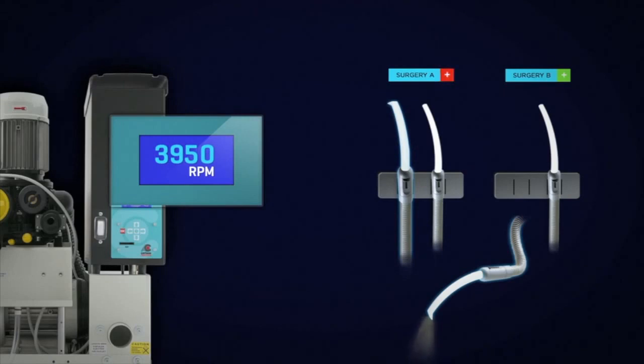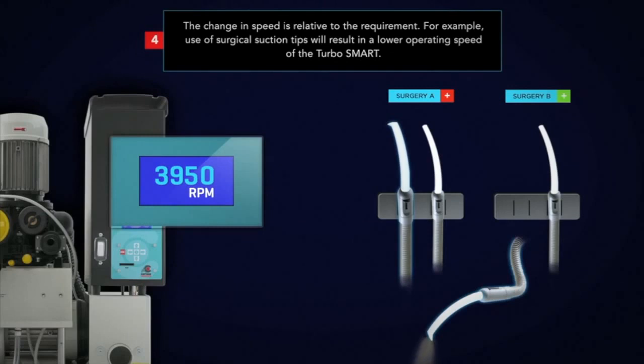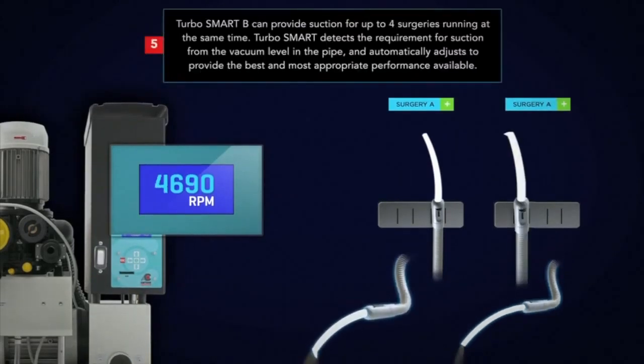TurboSmart is designed to provide a constant vacuum level. As the demand changes from the surgeries, TurboSmart will react to the varying demand. It will also respond depending on the requirements of suction. For example, when carrying out surgical procedures, this will result in a lower operating speed. TurboSmart is supplied as a 2 surgery unit, but with a software upgrade can provide suction for up to 4 surgeries simultaneously without loss in vacuum.